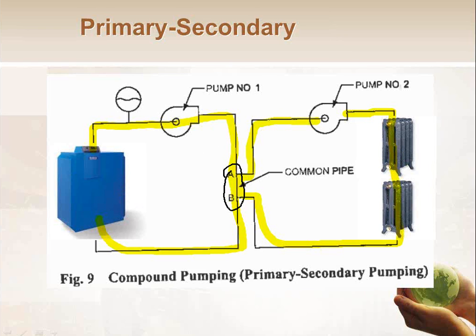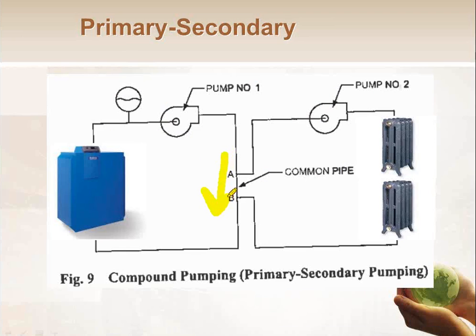So if I have pump 1 on and pump 2 off, so the boiler's running, but that particular loop on pump number 2 doesn't request anything, then the water is going to go that path, right? However, when pump 2 turns on, and assuming these pumps are the same size, the water will pull out this loop and go like this and back around, and there's going to be no water flow from A to B, right? If the two pumps are not equally sized, then I will have some water flow.